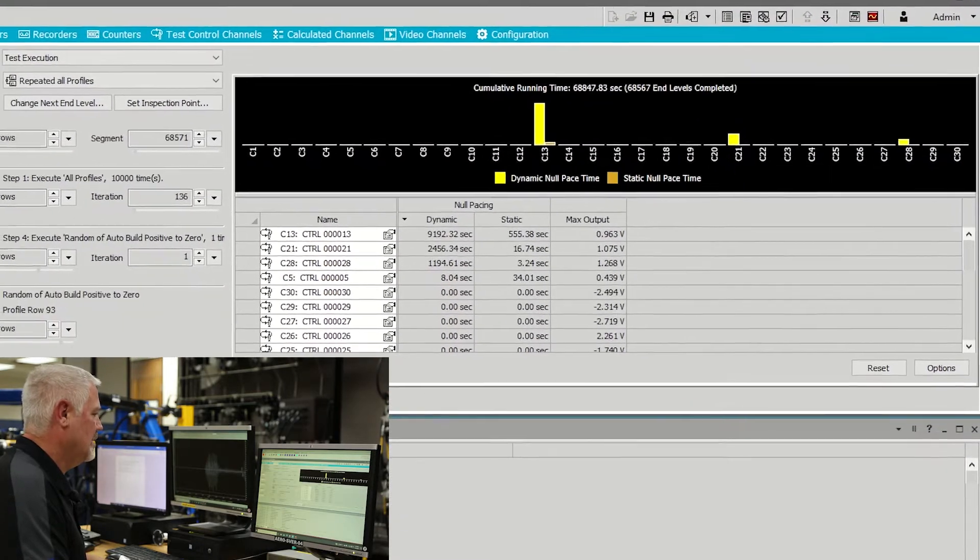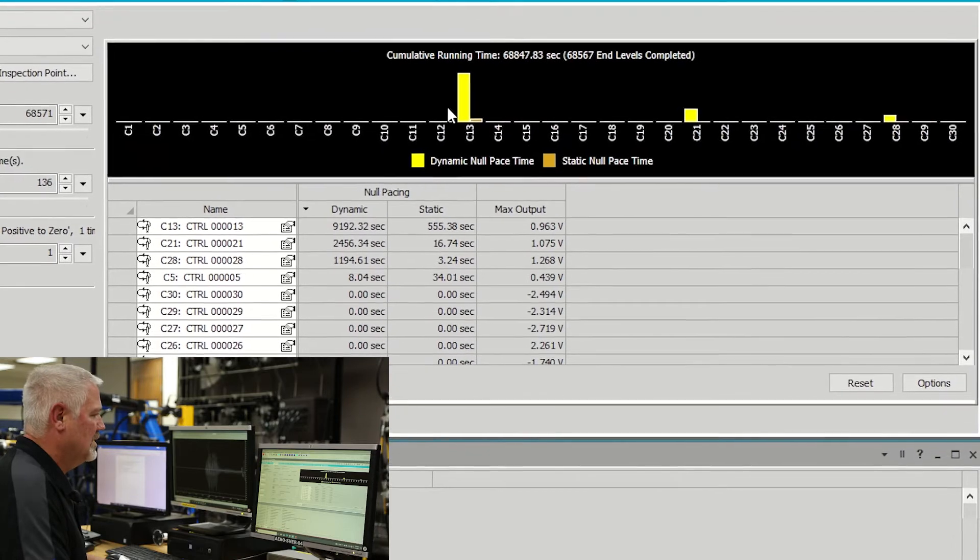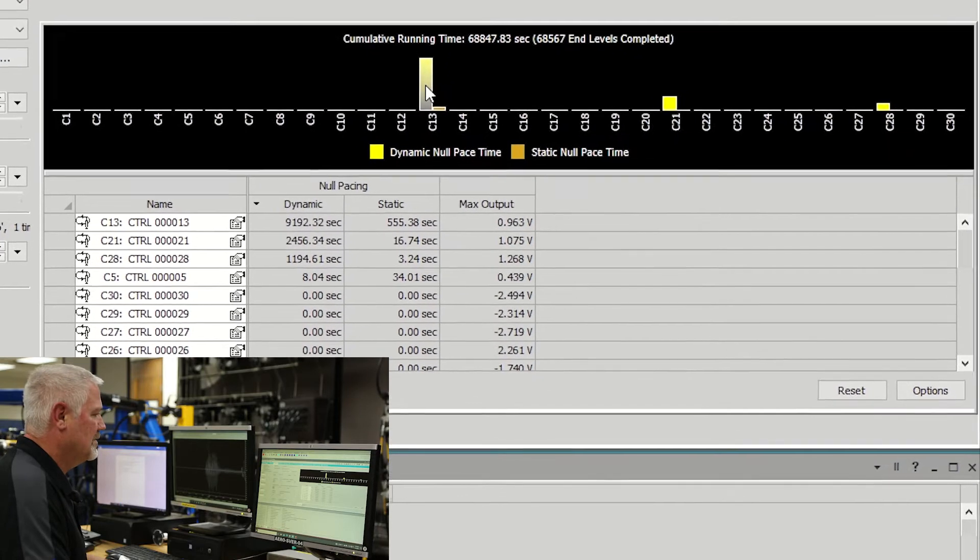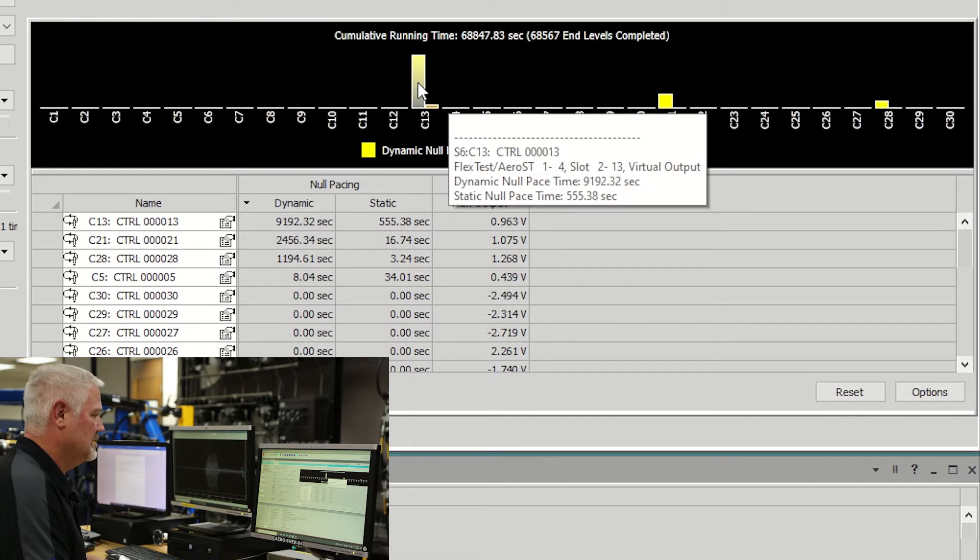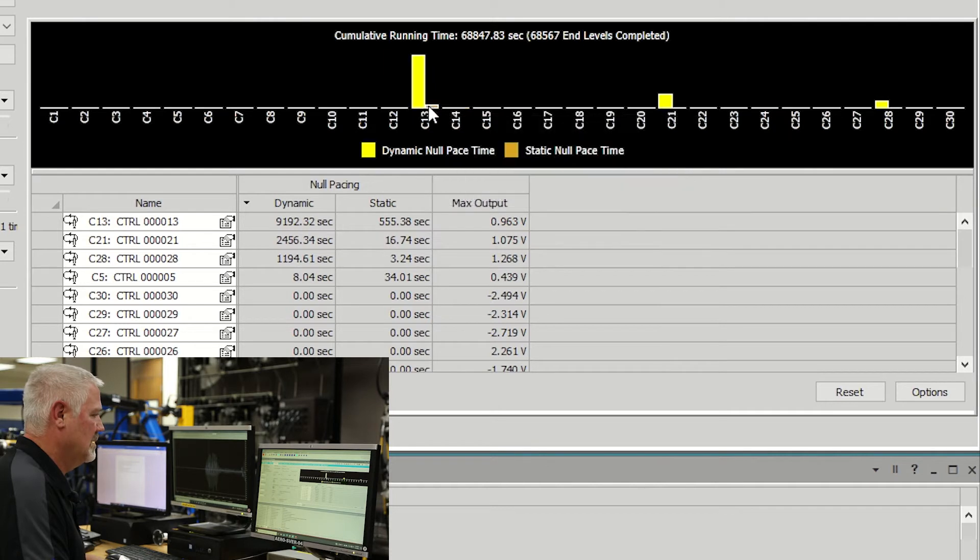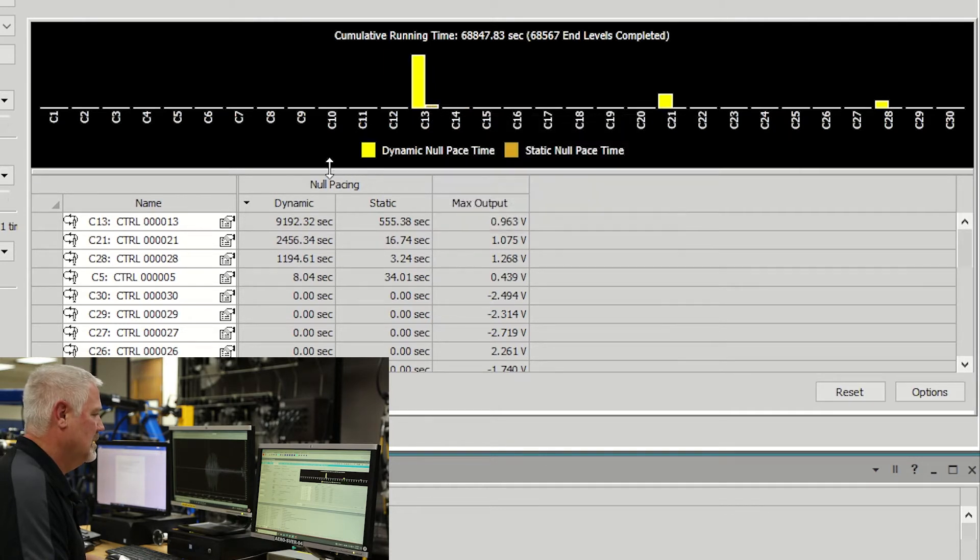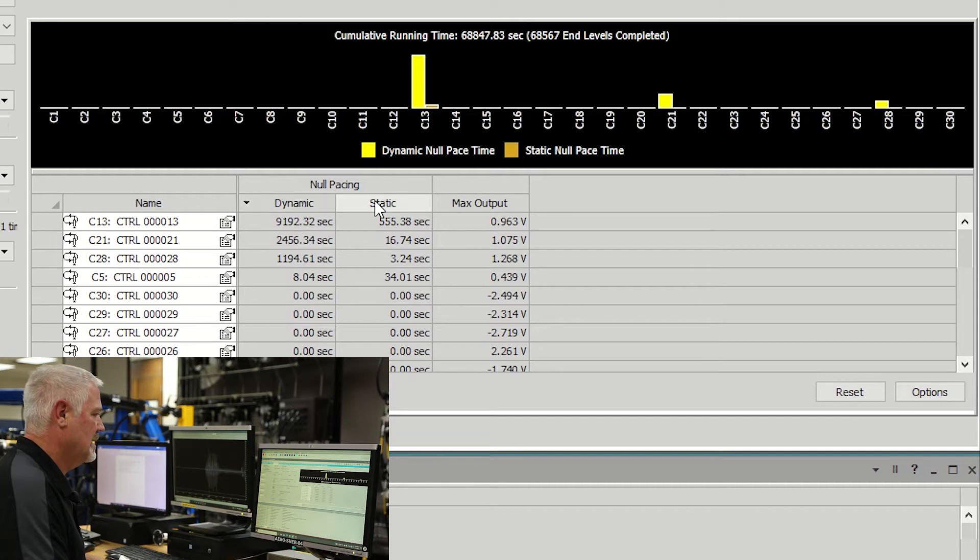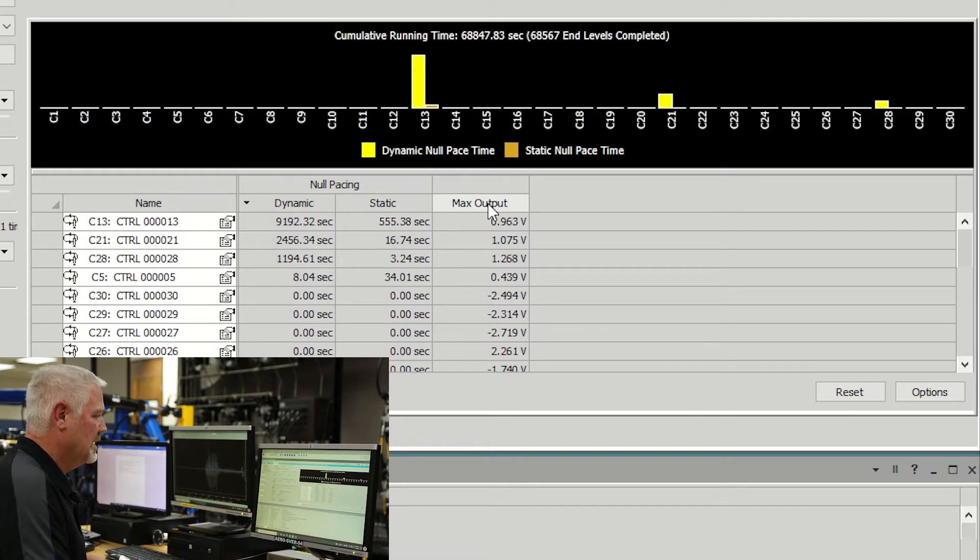The Analyzer tab on the Execution page contains a graph to show the total amount of time a channel has been dynamic null pacing, static null pacing, a table to show the total amount of dynamic null pace time, total amount of static null pace time, and the max valve output. The max valve output is a good indication of proper valve sizing.